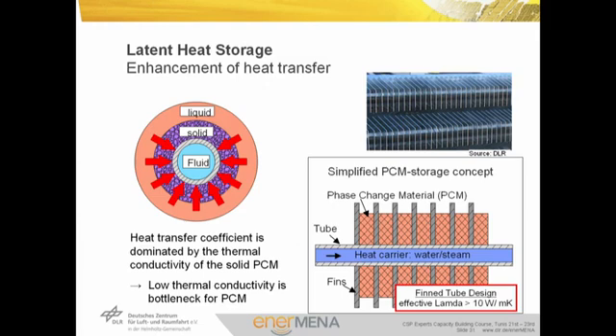All cost-effective latent heat storage materials show very low thermal conductivity. The main problem for the design of a latent heat storage system is the implementation of a heat transfer system that provides sufficient power during the charging and especially during the discharging process. During discharge, a solid layer forms around the heat transfer area, and the task is to transfer the energy from the phase change through this solid layer. Different approaches have been developed to ensure sufficiently high thermal heat transfer; one option is to use fins integrated into the storage material. The fins transfer energy from the storage volume to the heat transfer area.